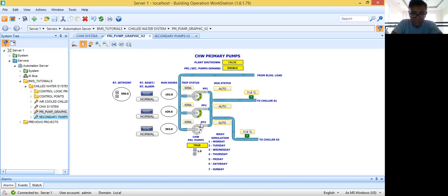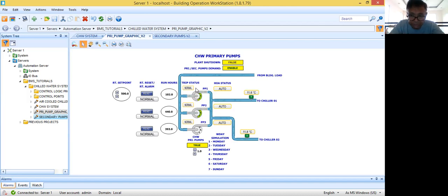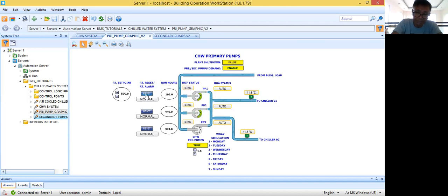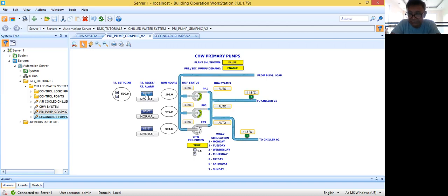The scenario here is two pumps duty, one unit standby. When you are writing the control logic program, you will always base it on an approved sequence of operation. Never write your control logic program without basing it on the approved sequence of operation. You cannot write it as you wish — you always look for the approved sequence of operation, which you can find in the mechanical specifications.